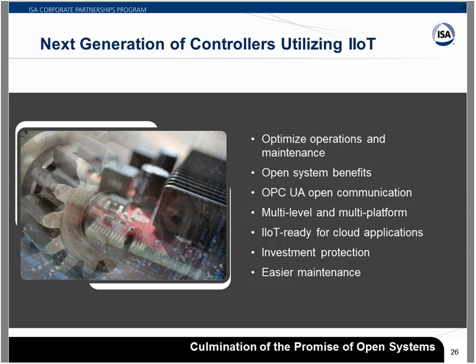OPC UA is a new platform coming out for us that's really going to help. It's divorced from the original Microsoft technologies present in the original OPC, and now we're seeing it able to be embedded into devices. Rather than a separate software layer sitting at the server level, we're able to have PLCs with OPC UA embedded. Honeywell's first PLC coming out now has OPC UA embedded directly onto it, eliminating one extra bill of material part, one extra thing to troubleshoot. It's just combined straight onto the controller.